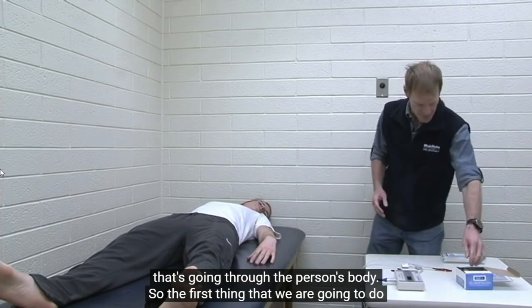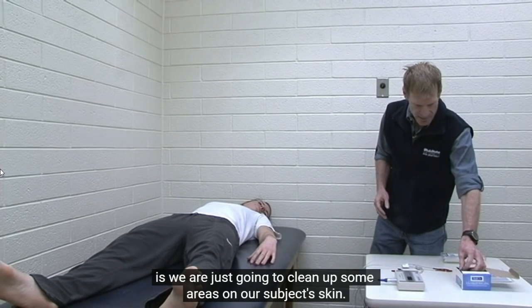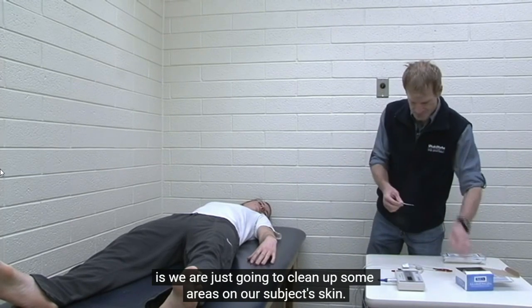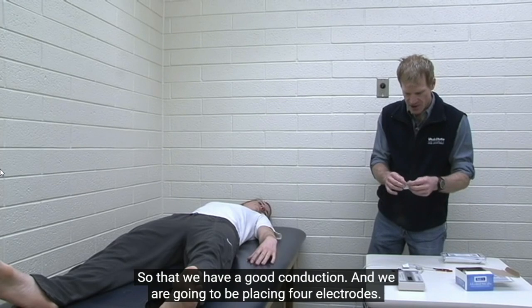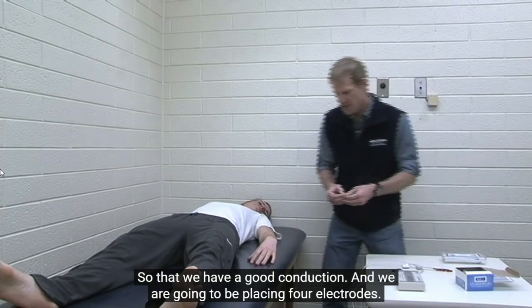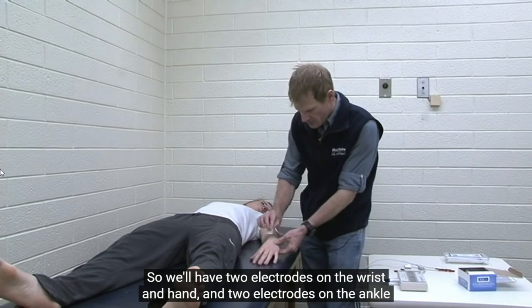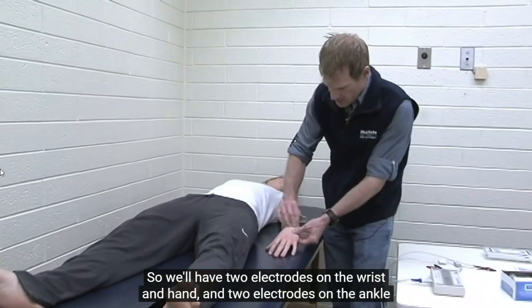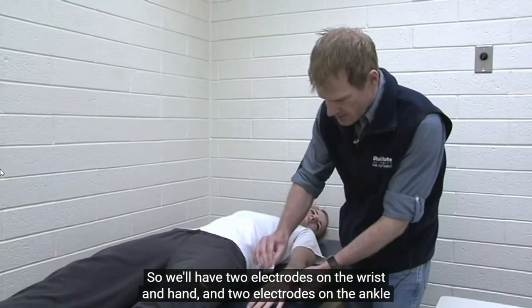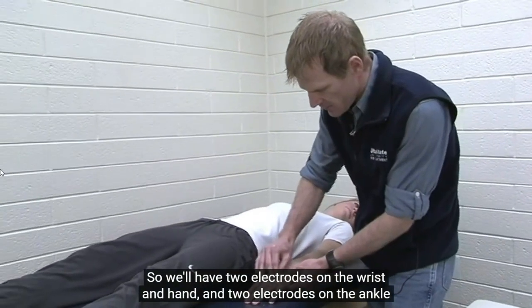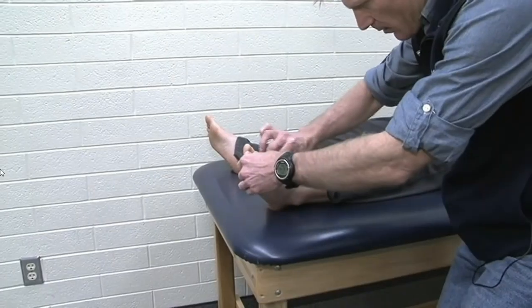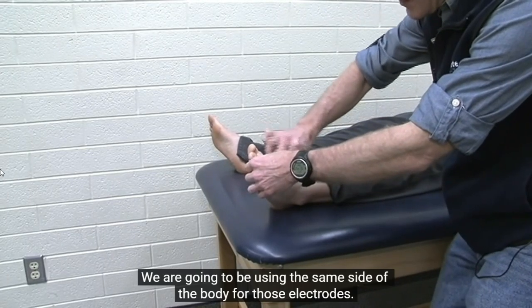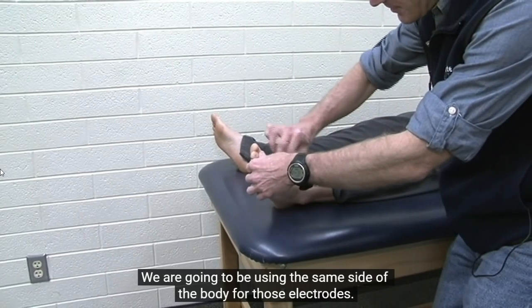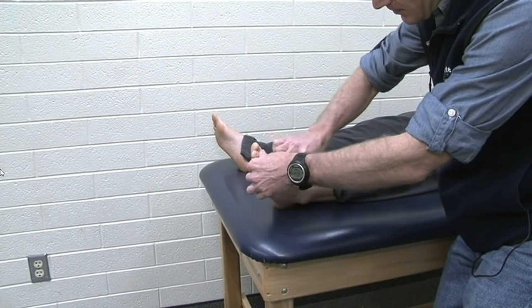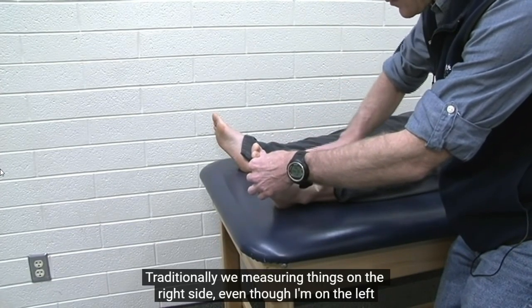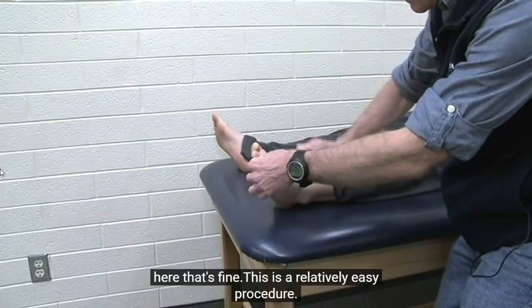So the first thing that we're going to do is we're just going to clean up some areas on our subject's skin so that we have a good conduction. And we're going to be placing 4 electrodes. So we'll have 2 electrodes on the wrist and hand and 2 electrodes on the ankle and foot. And we're going to be using the same side of the body for those electrodes. Traditionally, we measure things on the right side, even though I'm on the left here, that's fine.